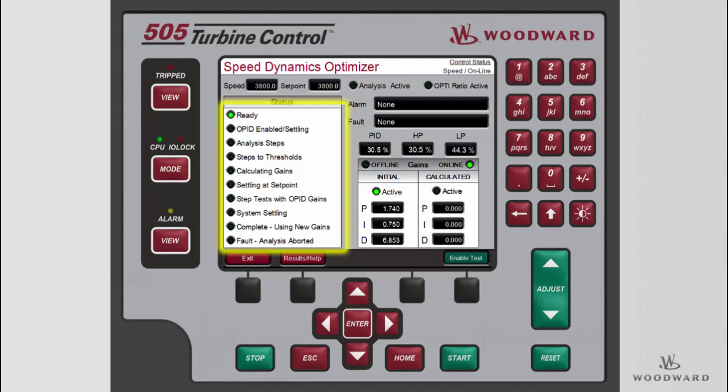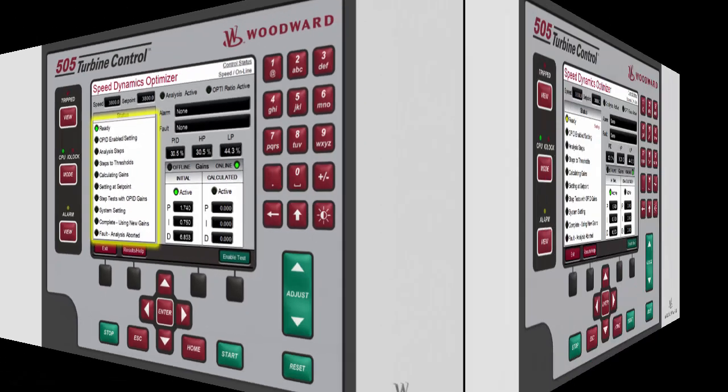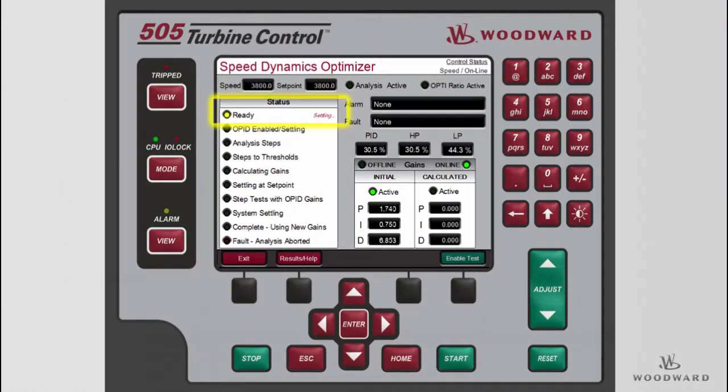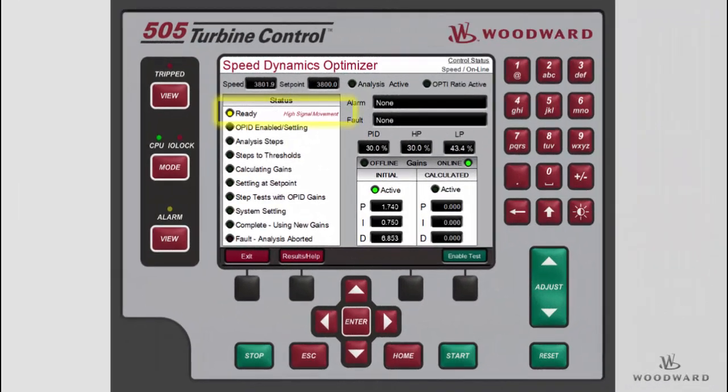The fault/analysis aborted LED indicates that the test was disabled and the speed PID is controlling speed at the initial setpoint using the initial gains. The ready LED indicates that the test can be enabled. When the speed setpoint is moved, the ready LED will turn yellow and a SETTLING message will be displayed for 30 seconds after the setpoint is moved, allowing the system to stabilize prior to starting the test. When the ready LED is yellow and a message for high signal movement is given, it indicates that the test will likely fail because the system is unstable or there is high signal noise on the speed signal. The signal noise must not be greater than 10% of the process or droop limit settings.